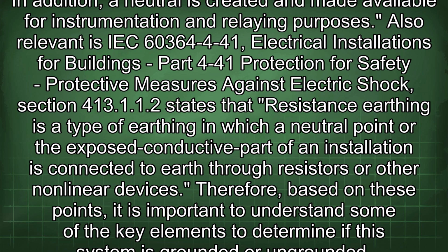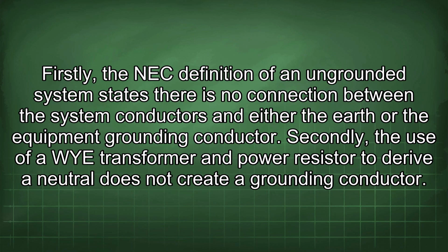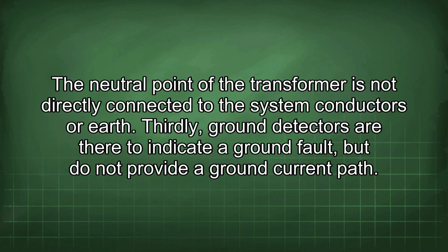Therefore, based on these points, it is important to understand some of the key elements to determine if the system is grounded or ungrounded. Firstly, the NEC definition of an ungrounded system states there is no connection between the system conductors and either the earth or the equipment grounding conductor. Secondly, the use of a WYE transformer and power resistor to derive a neutral does not create a grounding conductor. The neutral point of the transformer is not directly connected to the system conductors or earth. Thirdly, ground detectors are there to indicate a ground fault, but do not provide a ground current path.